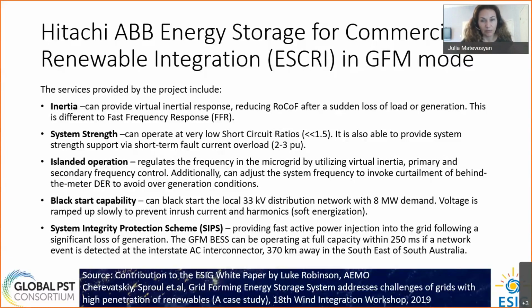It has black start capability, so it can black start a local 33 kV distribution network with 8 megawatt demand, and then again voltage is ramped up slowly to limit inrush currents and harmonics. Another functionality that it has, it's not related to grid forming capability. It could have been done with a grid following battery. It provides fast active power injection into the grid following significant loss of generation.